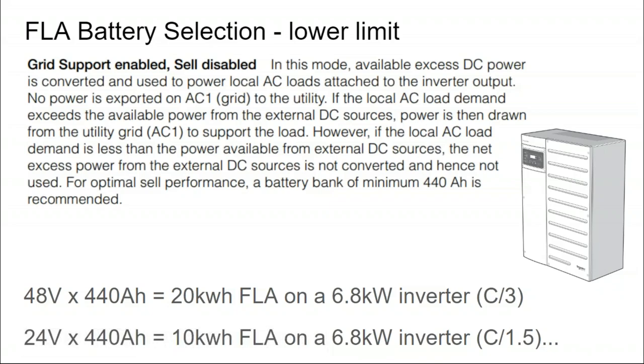What does that mean? Well, if you're doing a 48 volt battery configuration, which you probably are if you're buying this particular inverter since that's its highest voltage operation - and generally using higher voltages is the most cost-effective configuration. If you're buying a battery component and it says we work at 24 volts and also at 48 volts, designing the system around the 48 volt option, 9 times out of 10, is going to be the more cost-effective choice.